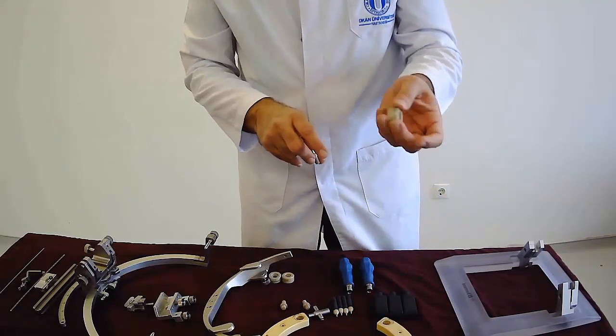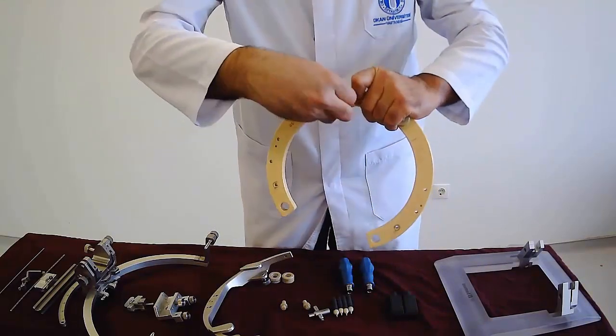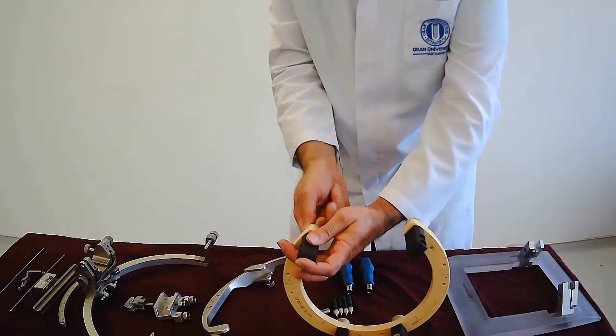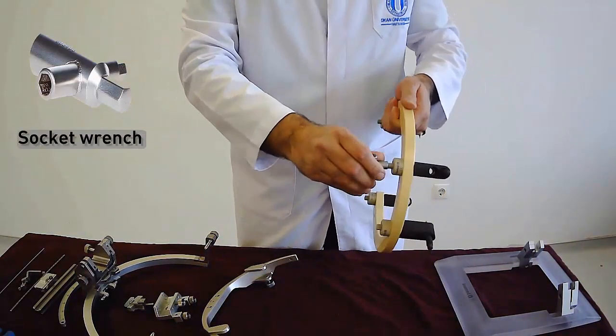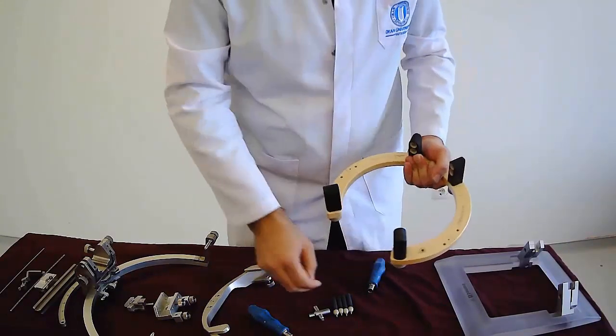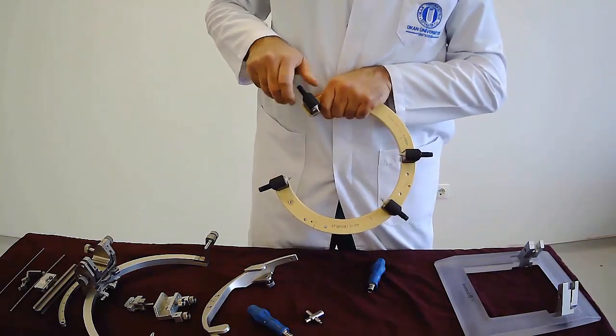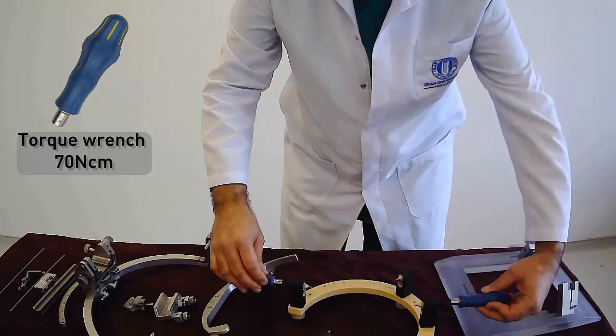The screws must be placed to the deep side of the nuts and tightened by a socket wrench. After the four fixing posts are implanted, the opti-pins are implanted into the holes of the fixing posts. The torque wrench with a 70 Ncm limit can be used for tightening the opti-pins.